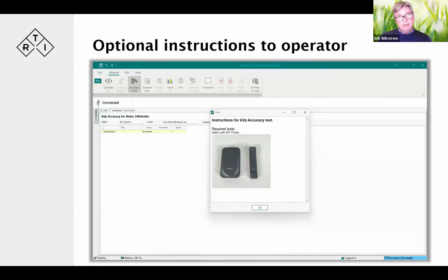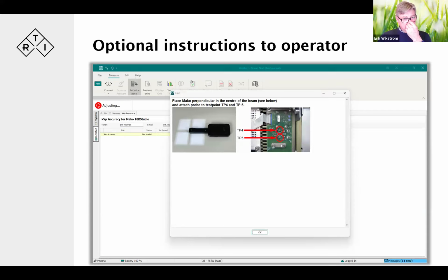Now, as that template loads, to ensure, or to increase the probability, that the user does the correct thing in the correct way, we can add instructions that pop up. And here, for instance, it says this is the tool that you need for this specific test. KVP accuracy test, this is the tool that you need. To advance, we need to click OK to get beyond this information, this hint. Again, when we move further, for this specific test, there's also information on how to position it, and if you have some other probes that you need to connect, so you're connecting it the right way. And here again, we need to click OK to get beyond this.